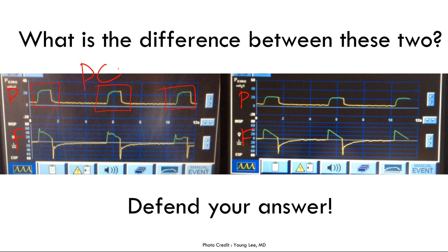Contrasting with the right waveform: looking at the flow, it appears smooth and exact — it looks like the independent variable, not a dependent variable. Everything looks preset, so flow is the independent variable — the target variable — because the waveforms all look exactly the same. Where flow is the target variable, this is volume control ventilation.